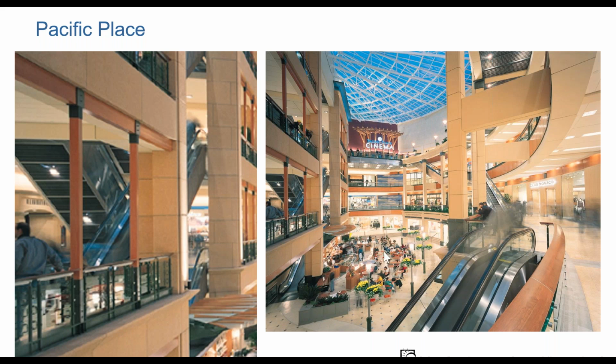Personally, the thing that vexed me the most, let's see, where is my spotlight? There it is. Under the escalators here, we had a series of tight beam downlight spotlights that would shine through this louvering material and highlight the escalators. It was actually quite lovely when it worked. And instead, what would frequently happen was these compact fluorescent tubs, which were just supposed to be emergency lighting, and in fact, they were supposed to be linear fluorescent on the side.